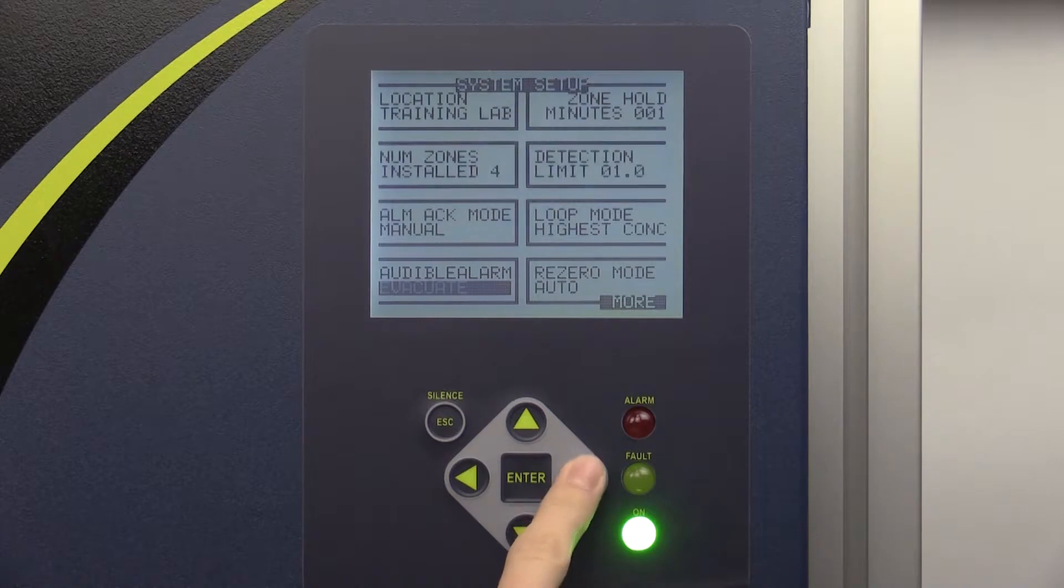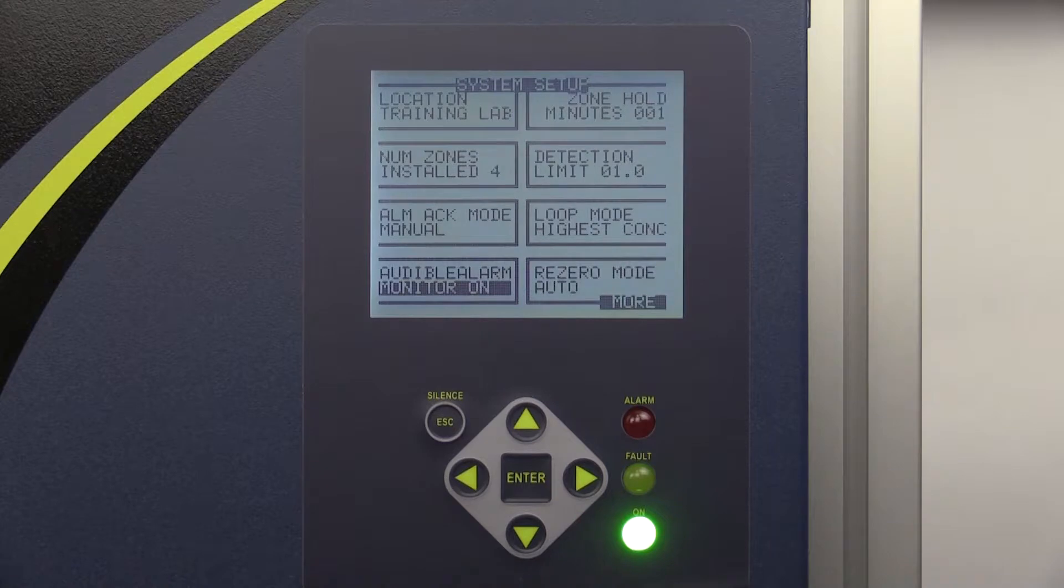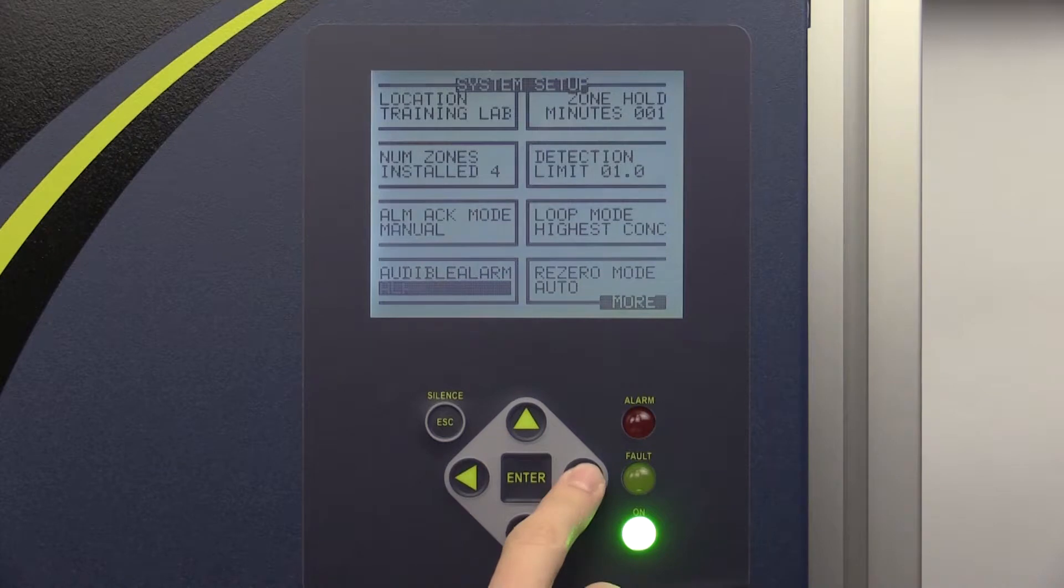The monitor on option causes an audible alarm to sound only when a critical fault occurs that stops the unit from monitoring. When the unused option is selected, no audible alarm will sound. When the alarm option is selected, an audible alarm will sound any time an alarm goes off. When the fault option is selected, an audible alarm will sound any time a system fault occurs.